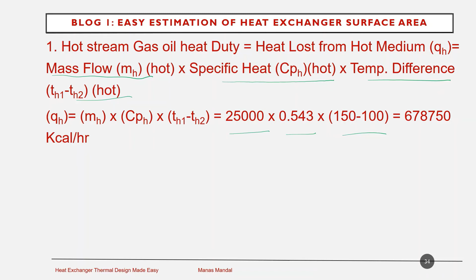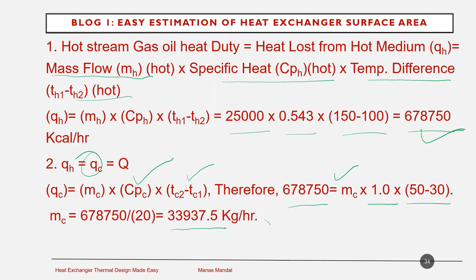QC is not known. QC is the cooling water heat duty, which is not known, but QH has to be equal to QC. So QC is nothing but 678,750. CPC is also given, and TC2 minus TC1, the temperature difference of the cooling water, is also known. So MC is unknown, but 678,750 equals MC multiplied by 1 multiplied by 50 minus 30, which will give us 33,937.5 kg per hour of cooling water.